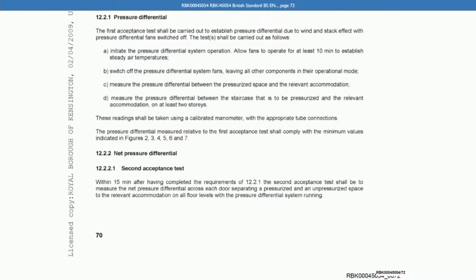Now, the second acceptance test is called the net pressure differential test. We can see that at clause 12.2.2 at page 72 of the British Standard. If we can go back to that, RBK 00045054. So within 15 minutes, having completed the requirements of 12.2.1, the first pressure differential test, the second acceptance test shall be to measure the net pressure differential across each door, separating a pressurised and an unpressurised space to the relevant accommodation on all floors with the pressure differential system running.